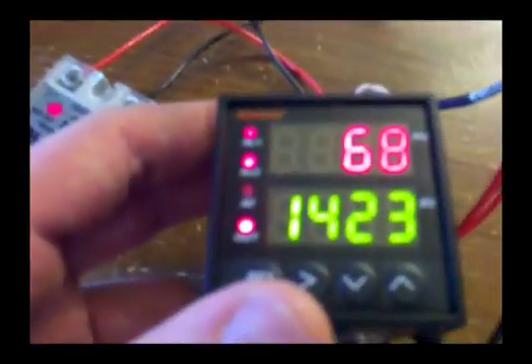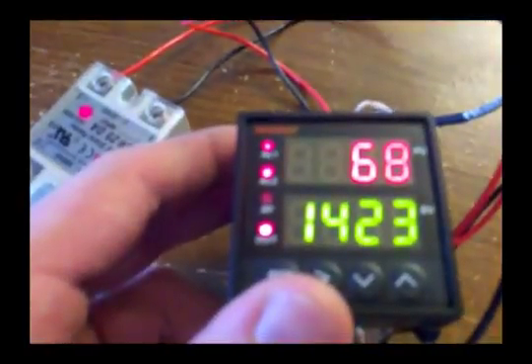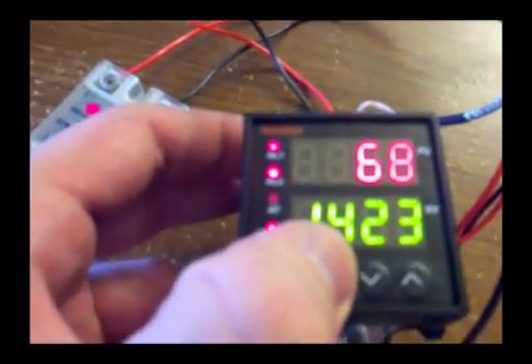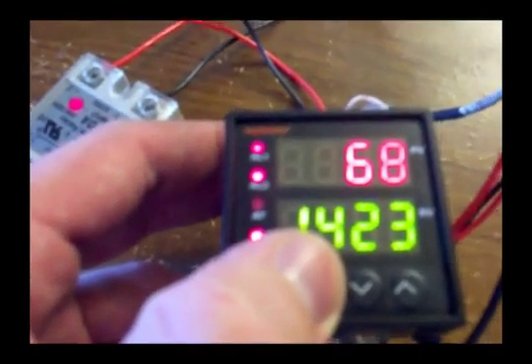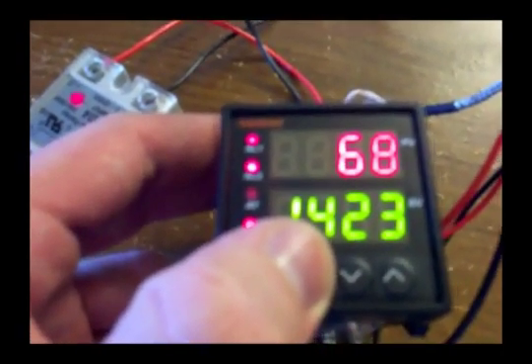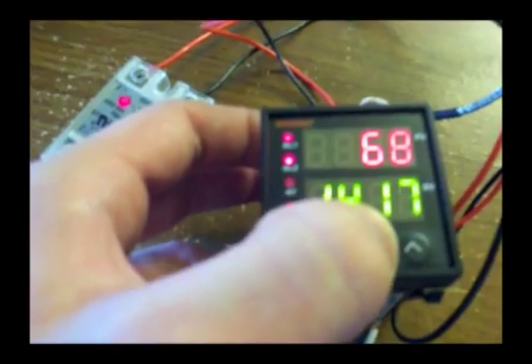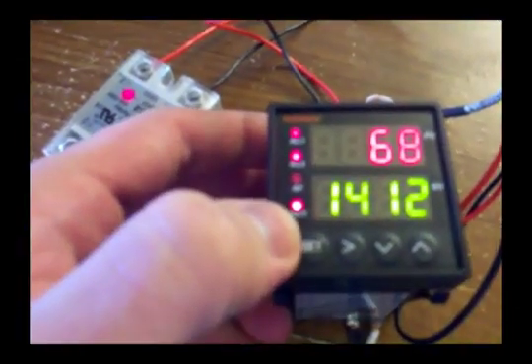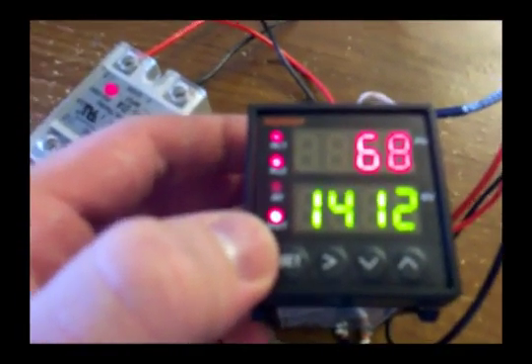If you're using this kiln controller to cool something down, it means that your solid-state relay is connected to some kind of cooling system. And if you put this set value higher than your measured value, it's not going to do anything, because it's trying to cool stuff down, and if it's already cooler than what you're setting it at, it doesn't need to do anything for you. Same thing with heating something up. If I were to set this set value lower than 68, it's going to blink on and off, but it's not really anything it can do, because it's set internally to only heat stuff up, not to cool it down.